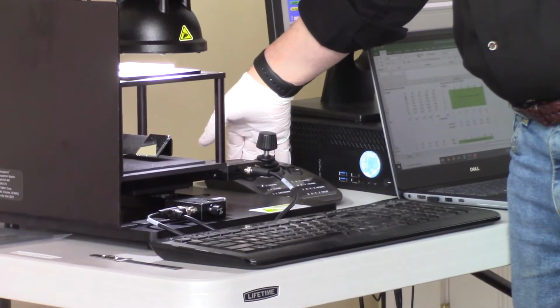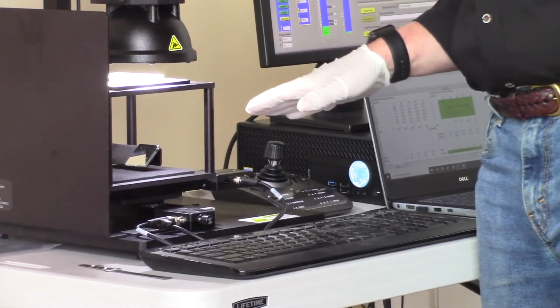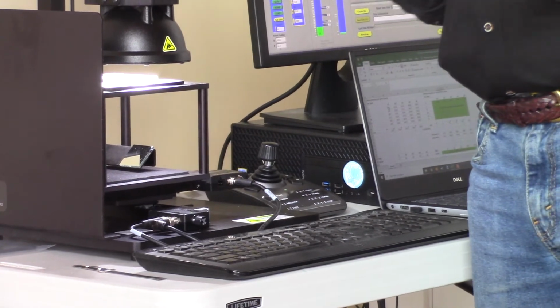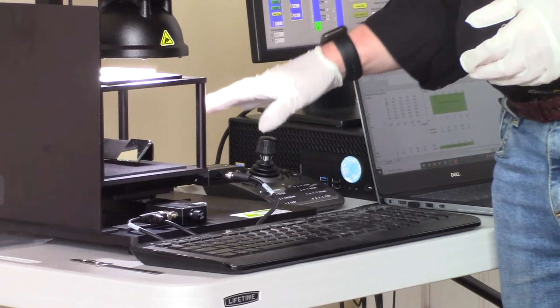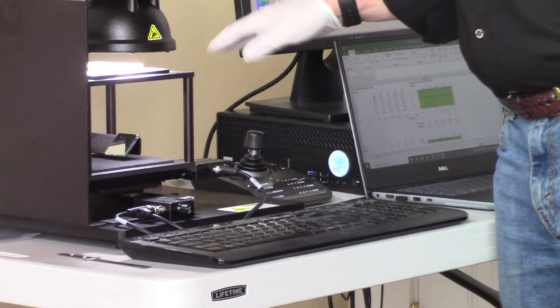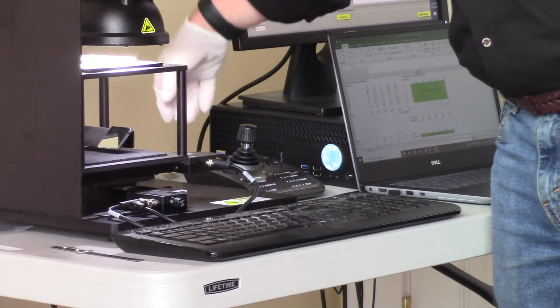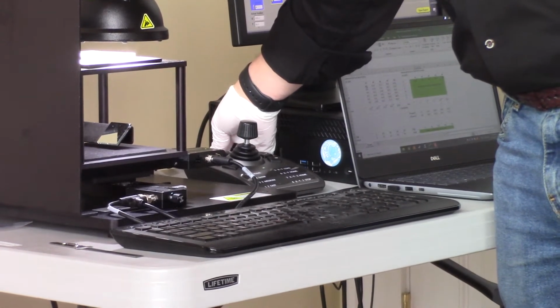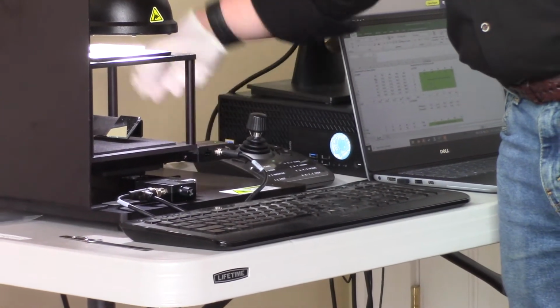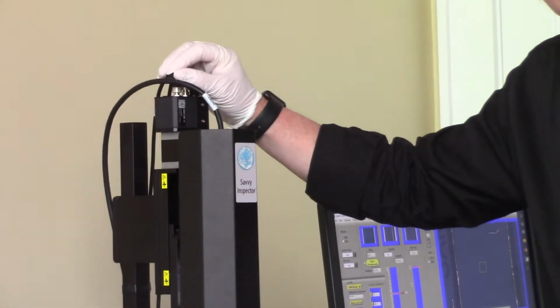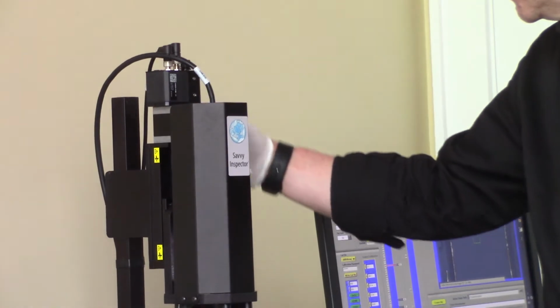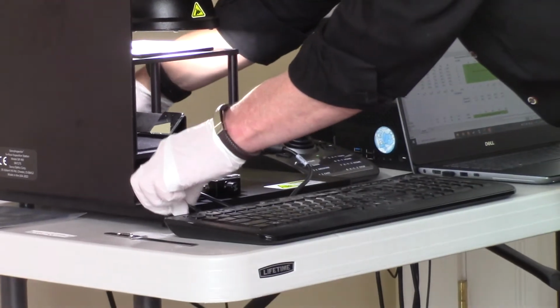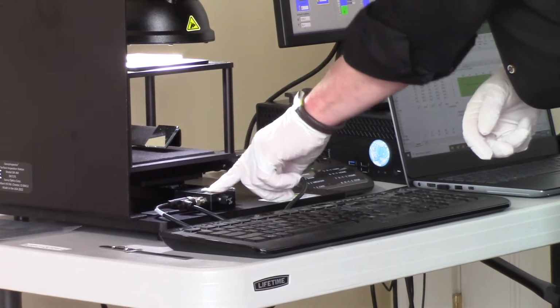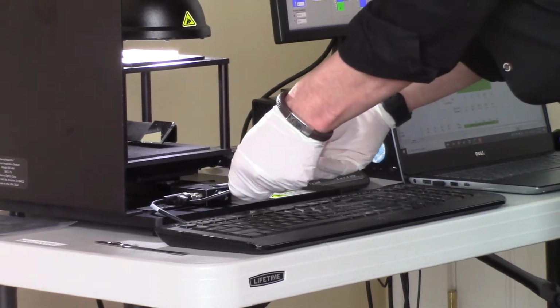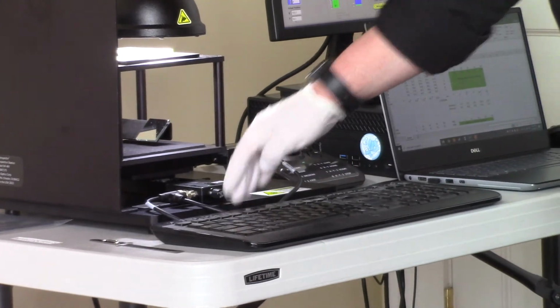The way the cabling works is this is an X system. So there's X systems and T systems. The T systems are slightly different. Most of the systems going forward are going to be X systems. So the X staging, this is an X joystick. The joystick is connected to the computer via a cable. It is also connected via a second cable to the Z stage. The Z stage is then connected via another cable that's run underneath the system to the Y stage. And then the Y stage is connected to the X stage via the short patch cable. Okay? So when we ship it, we have to change the cabling, so you may have to re-cable it when you get it set up.